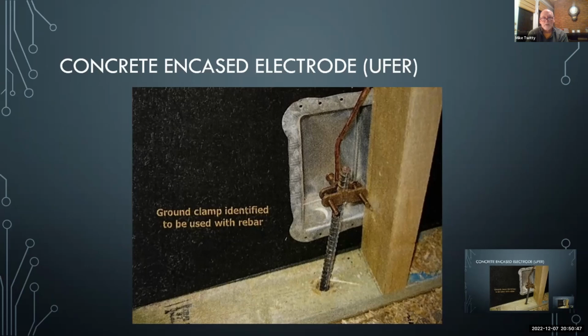It can also be a number 4 bare copper conductor, like the grounding electrode conductor you're seeing coming to that rod. That can be the Ufer in the concrete. But now you ask, could a ground rod be used? I suppose it could, but who's going to use a ground rod in a footing when rebar is a whole lot cheaper? They're going to use what's there. So it's using the foundation steel for the grounding electrode.